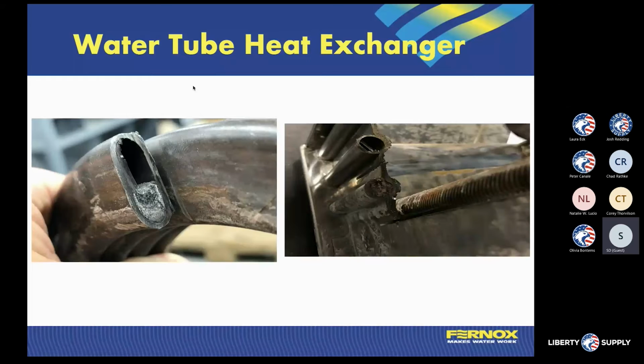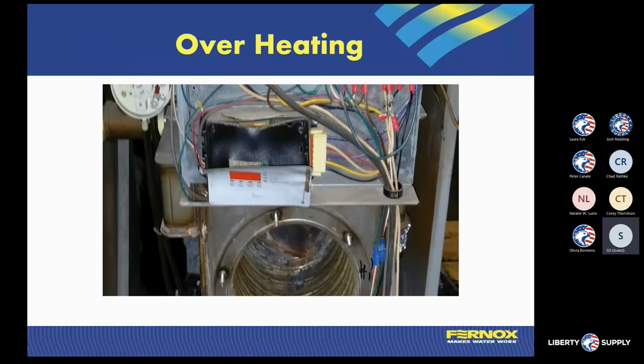The other byproduct is because we're now going to start to overheat that water because we're slowing the flow down. Water is now sitting in that heat exchanger for a longer duration. We can start to overheat components. We already mentioned venting. This is an application where it overheated the controls and melted the controls right off of the side of that heat exchanger. So those are all byproducts or component failures of that water quality not being proper inside of that heat exchanger.